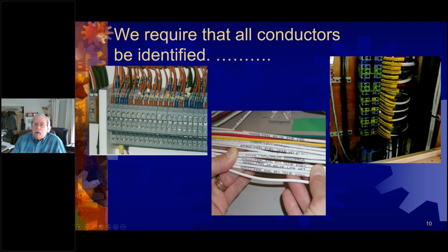A lot of manufacturers will use heat shrink tubing with printed identification on it. That's a great way to do it. Just remember, from the service side, if you have to re-terminate that wire at any point, you may want to relabel it or try and slide the heat shrink up the conductor a little bit so you can get a new terminal on the end.